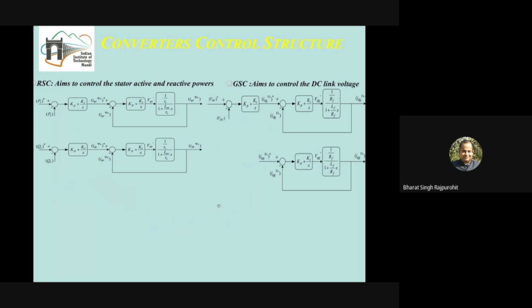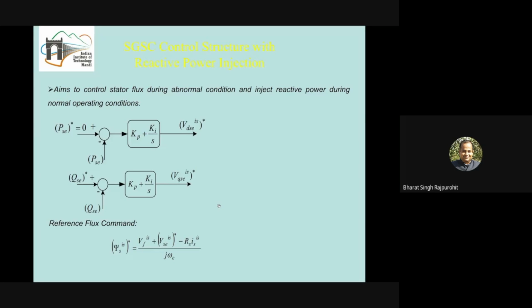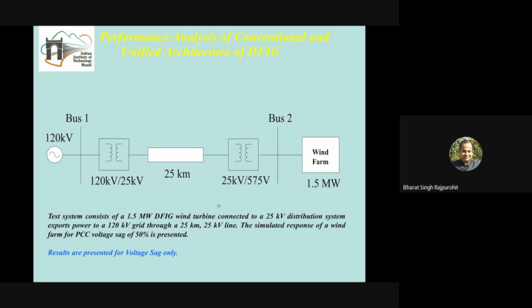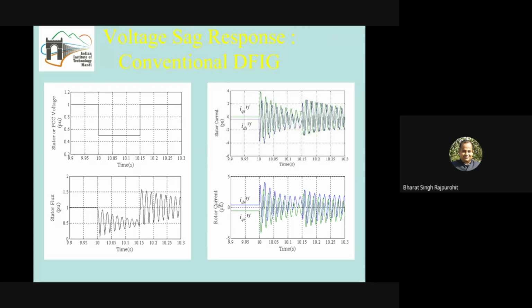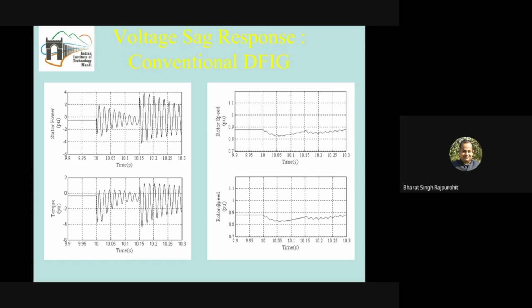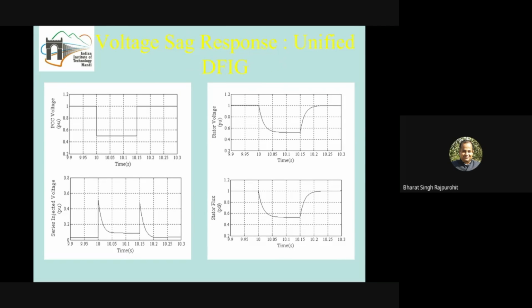We have done some study on this, and I will skip some of the control structure here. I will just show you the results for a very small wind farm on a 120 kV system where a 25 kilometer distribution feeder is there. You are able to see a voltage sag of 50%, and then some oscillations in the current, the active and reactive power, and the torque. But when this series grid side converter is used, these oscillations are damped out, and the responses are simpler and without oscillation. So this can also be achieved.